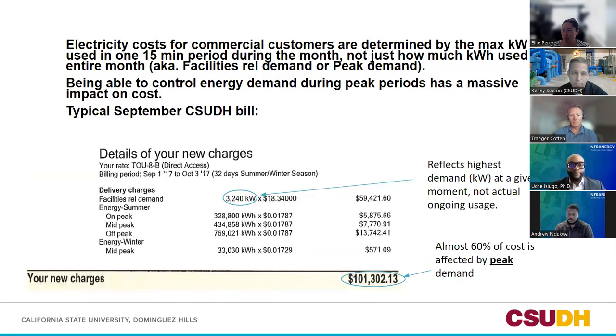What does it look like on your bill? So here's a bill from 2017. Peak demand: Uche had said it could be up to 50%. We're finding that it's 60% or more sometimes. The battery helps, so that's not as bad. So here's 2017. We peaked at 3.2 megawatts, or 3,240 kilowatts. The price at that time for peak demand charges was $18.34. Of our $101,000 bill, $60,000 was for peak demand charges in 2017. Next slide.